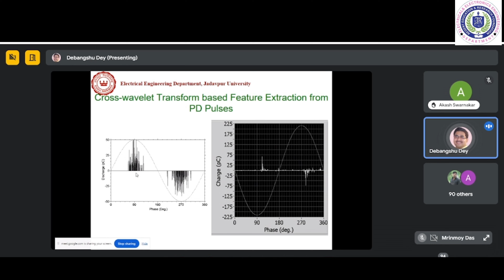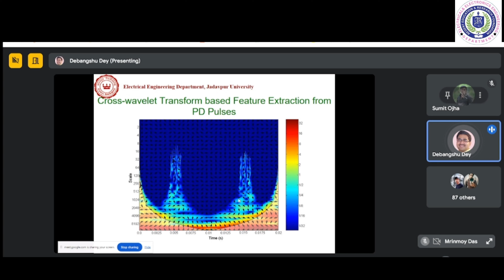This tells us that partial noise may be present all over the 20 millisecond cycle, but partial discharge occurs only at some regions. So whenever we correlate two waveforms, where they have some similarity is this region. Noises, in most cases, are uncorrelated, so they will not give an indication here. Only the partial discharges, occurring at the two half cycles, show up in the image. That is the purpose of placing our signal processing tool in that way, and that is the philosophy behind this.